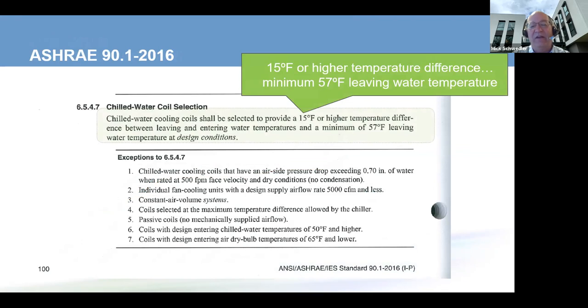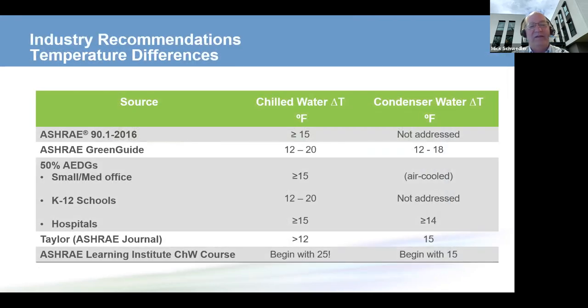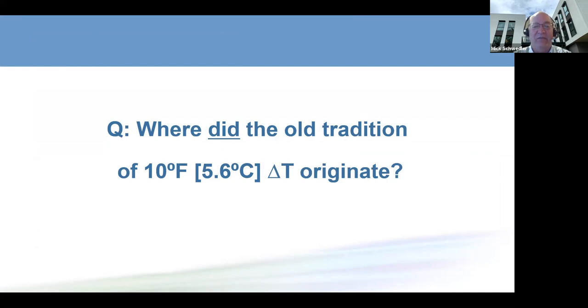We have that 15 degree delta T coil selection. All of the industry recommendations, the green guide, the advanced energy design guides, the chilled water system learning course, they say increase the delta T's, reduce the flow rates. So where in the heck did 10 come from?